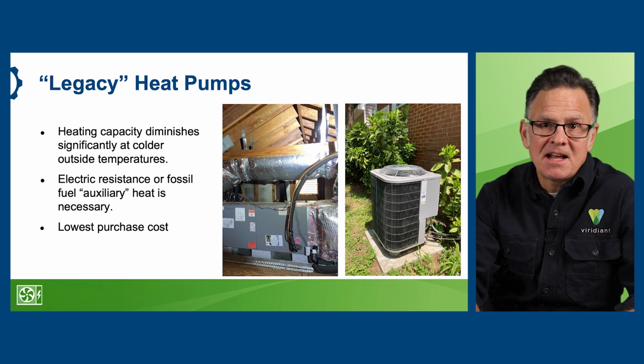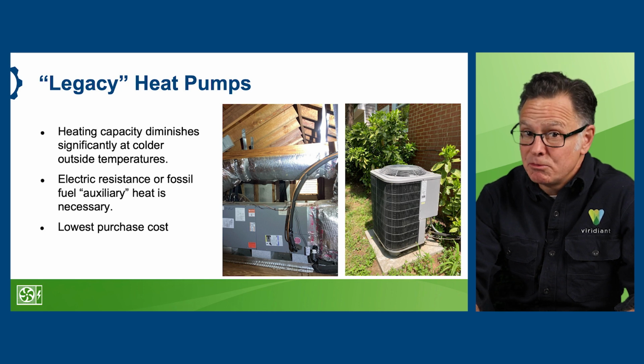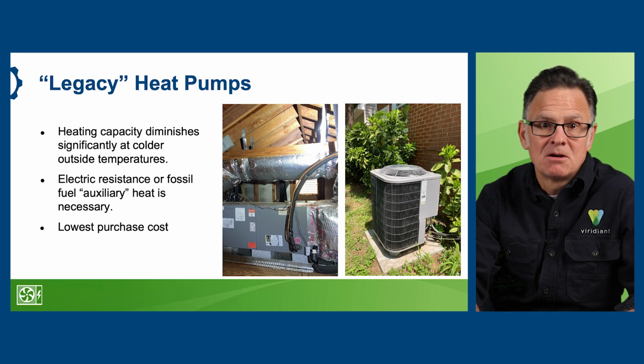The key challenge for standard heat pumps is the extent to which they lose heating capacity at colder outside temperatures. As it gets colder outside, they require auxiliary heat to deliver enough BTUs to the home. This is the emergency or backup heat that folks hate paying for. Usually it's electric heat strips mounted in the air handler, but the auxiliary heat can also be some sort of fossil fuel-fired system. That might be a dual fuel heat pump that basically has a built-in furnace, or it could be a heat pump installed where the home also has a separate furnace or boiler system.